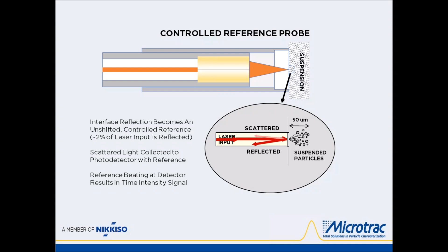The reason why we do it that way is because it boosts the signal, and the benefit of boosting that signal is we can get a much higher, wide range of volume percent analysis capable of that. So we only care about the light that's coming directly back at us, 180 degrees. The particles that move toward us and the particles that move away from us, those are the ones that shift the laser light red or blue.